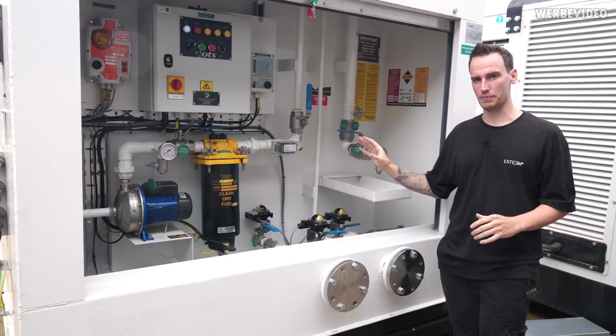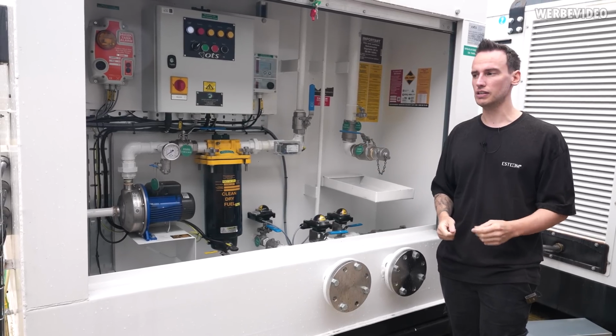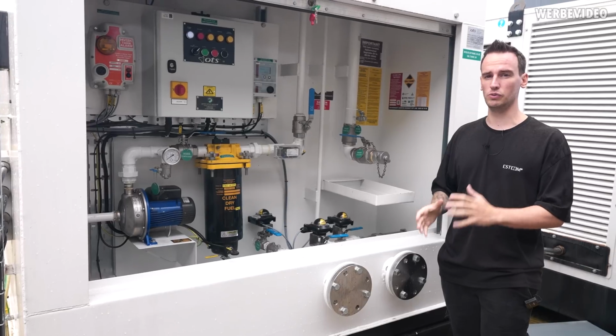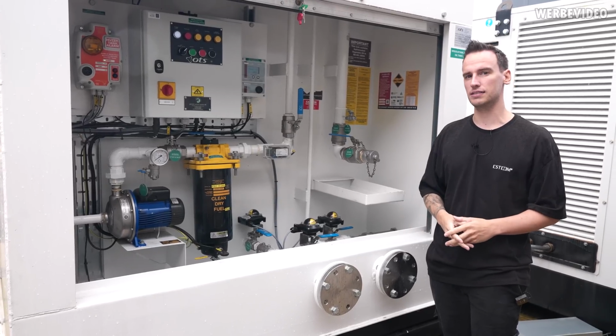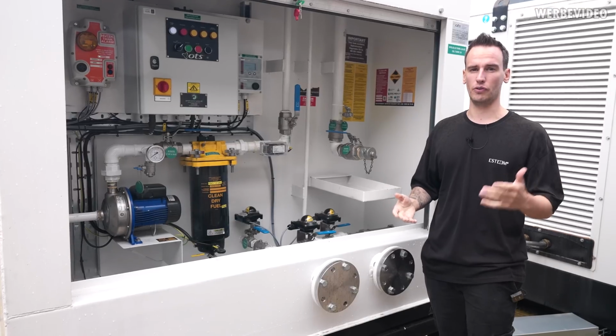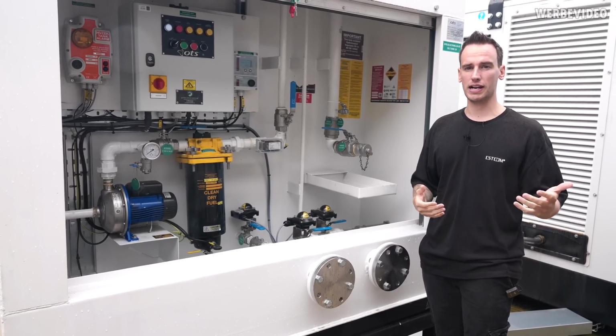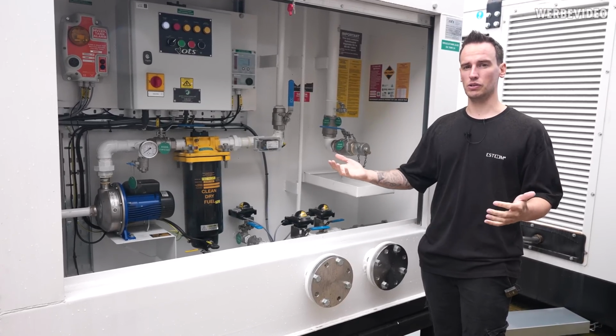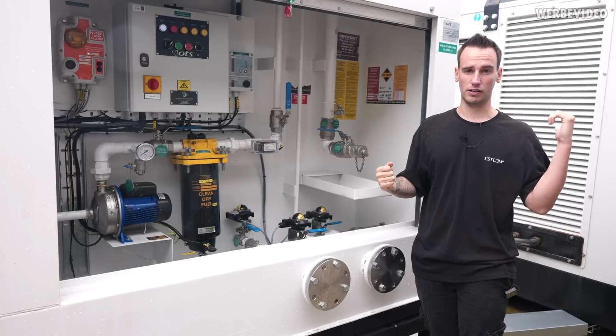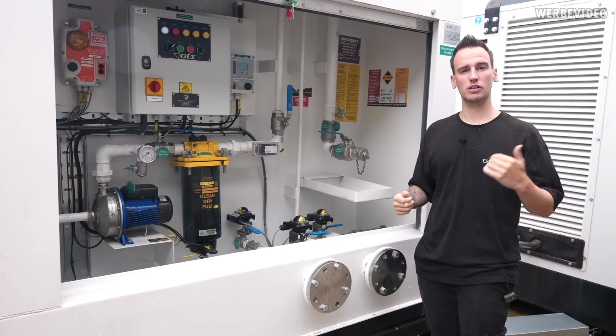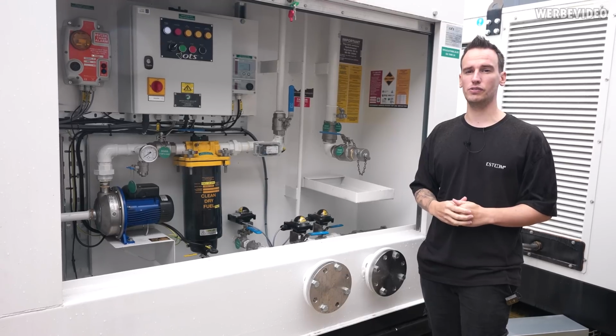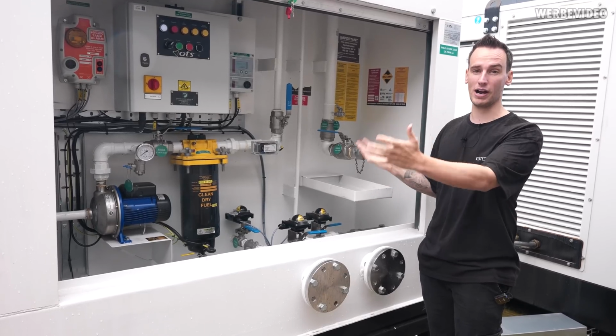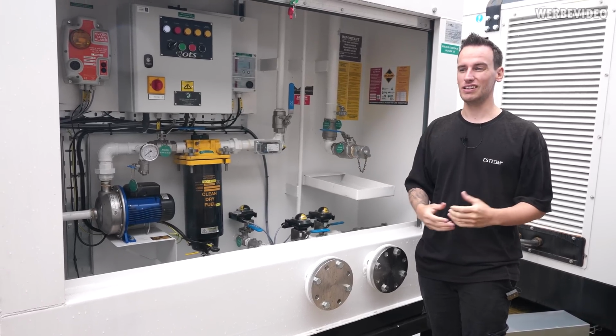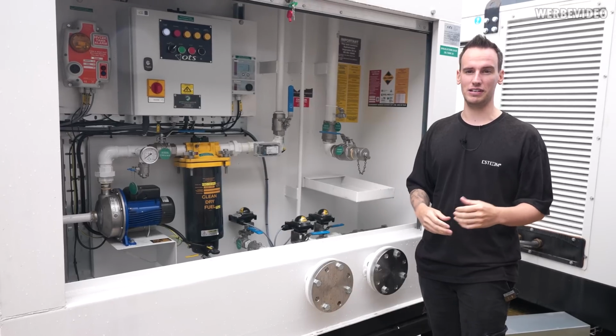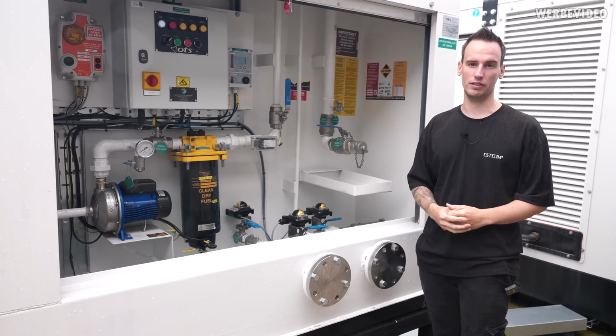This tank has a capacity of about 7,700 liters, enough for constant full-load use for about 3 days. But as a tier 4 data center, they have contracts with fuel suppliers, so if the generator starts running, they just call the supplier, and within a few hours trucks line up to refuel, so they can theoretically run for an infinite amount of time on this fuel.